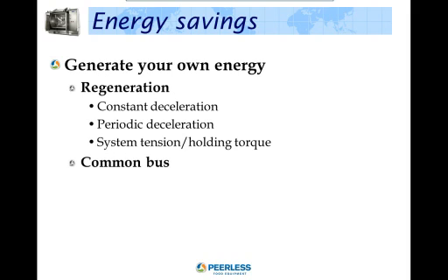Overhauling is a condition where the mechanics or the physics of the load mechanically cause the motor to attempt to turn faster than the motor speed the drive is commanding, and the drive is used to slow down the motor speed. This overhauling condition may exist in several types of applications. Constant deceleration. When a load such as a decline conveyor operating under the influence of gravity will overhaul the motor speed, and the drive is used to control the conveyor speed to a slower level than what the natural physics of the application would produce.